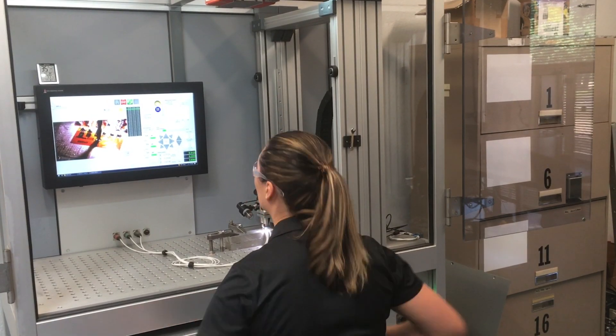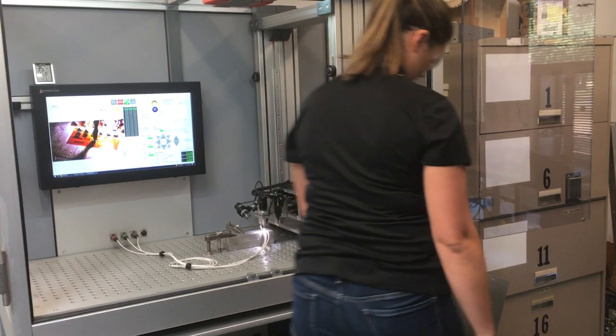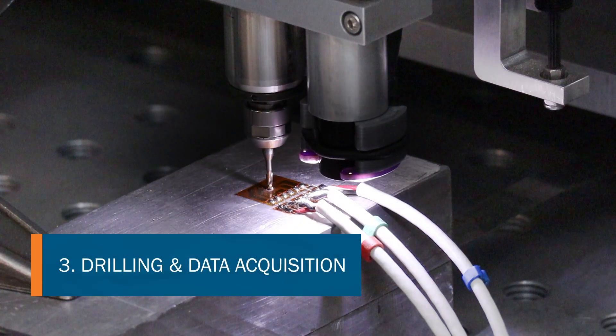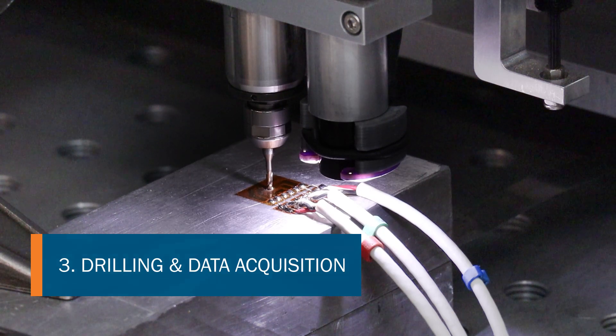After pressing START, everything is hands-off as the DART takes over the measurement, incrementally removing material and acquiring the strain data necessary for residual stress computation.